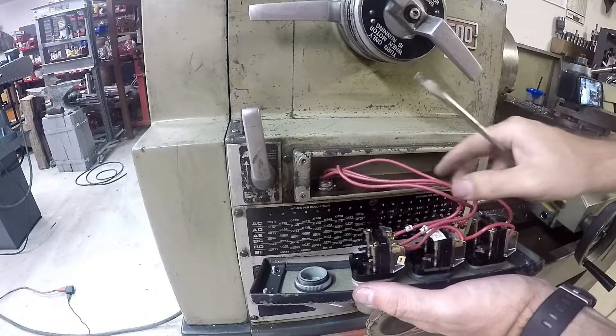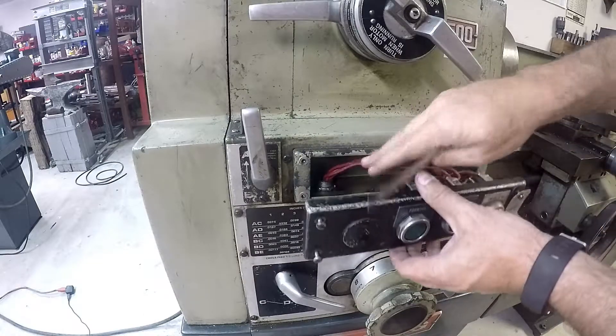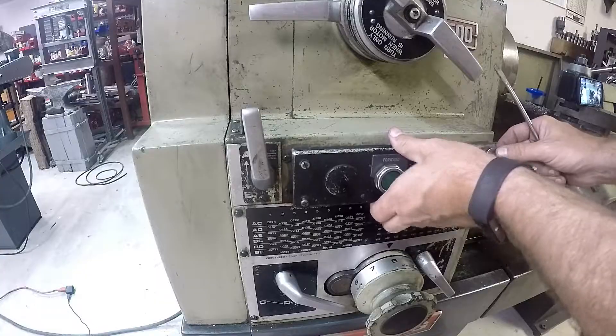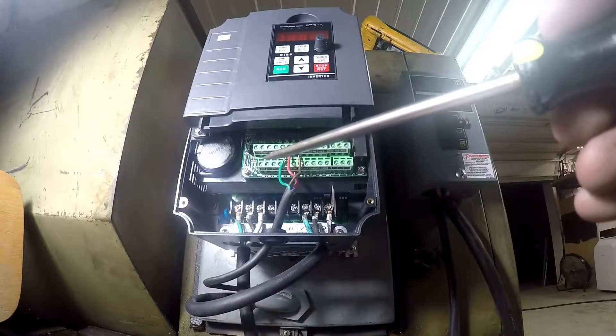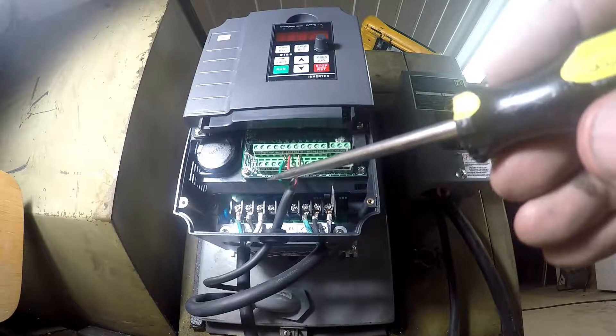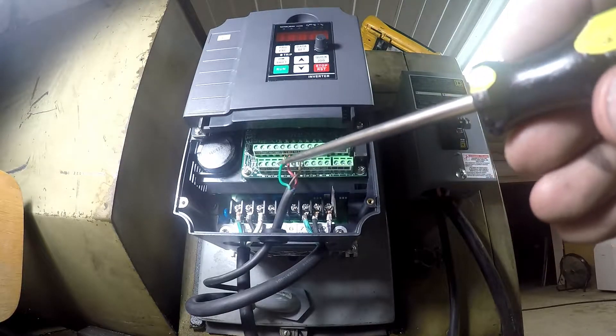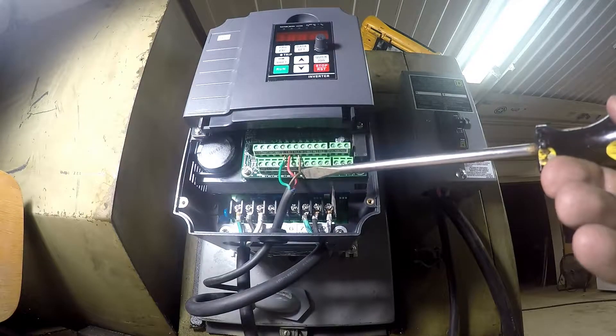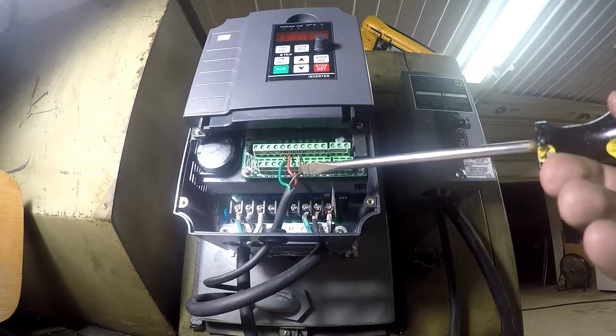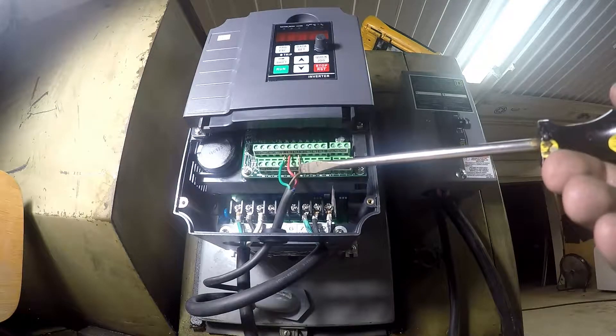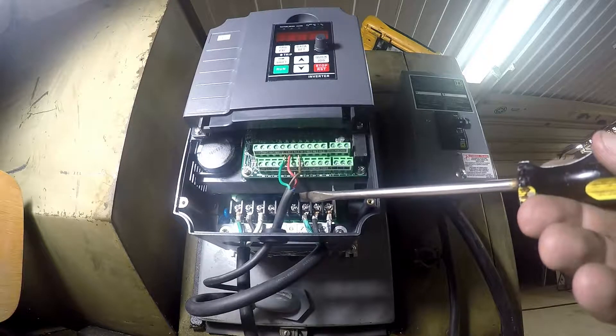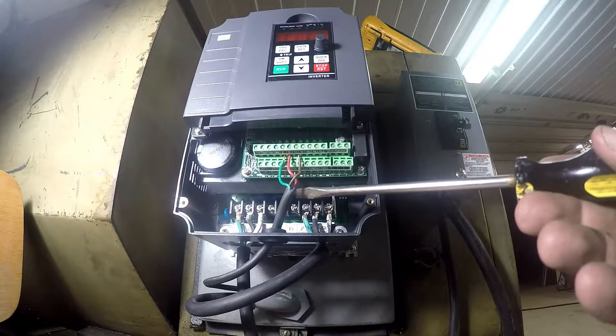From that front button panel, this green wire is hooked up to the forward button, the red wire to the reverse button, and this brown wire is hooked up to the emergency stop, which is really just any stop anytime you want to stop the motor. Then this blue wire is actually the common rail across all of them. From here you can see the green wire going into S1, the red wire going into S2, the brown wire going into S3, and the blue wire going into common.